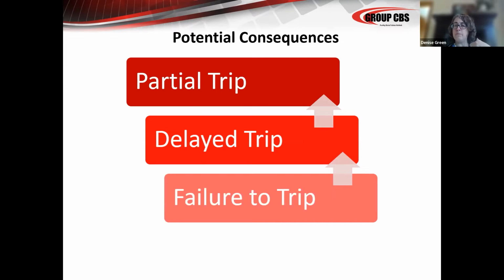The breaker that I'm talking about, they got struck by lightning, and they had lost vacuum in one of their interrupters on a PowerVac. And the breaker opened, but because there was no vacuum, the gap was only 5/16 of an inch or whatever the gap was on that particular interrupter, and the entire breaker burned down. I don't know if you're familiar with a PowerVac, but it's got the orange insulation completely on each pole. The entire insulation was burned and gone. It welded a hole through the front cover of the breaker. It welded a hole in the side of the cubicle, and turned into an extreme arc flash fire event.